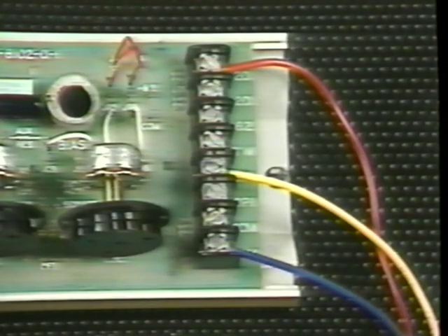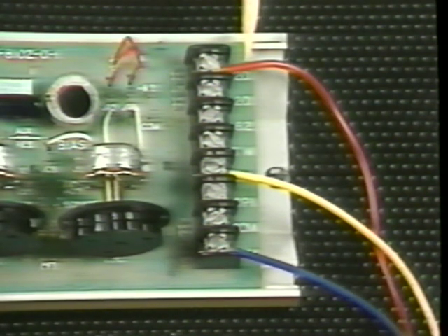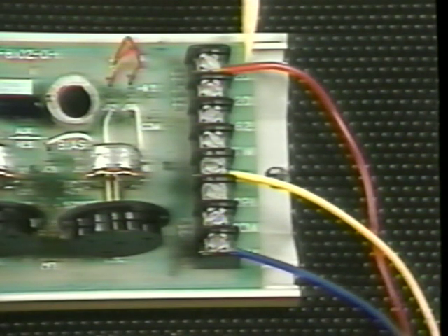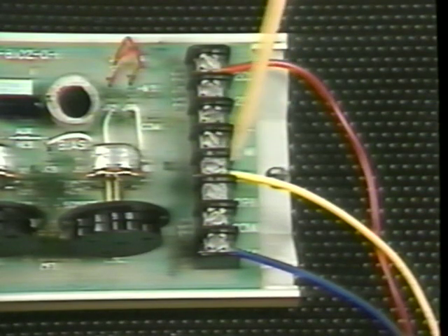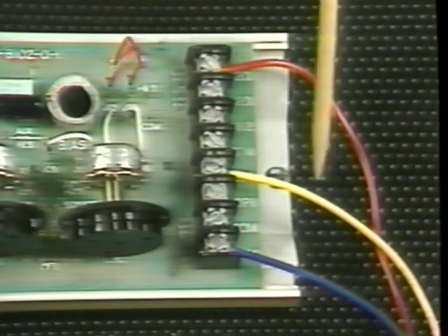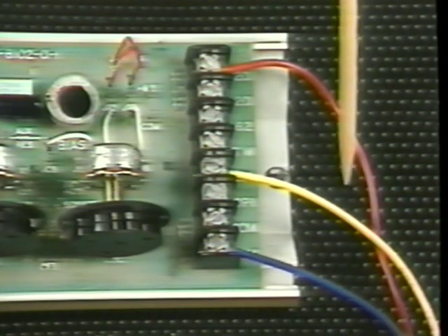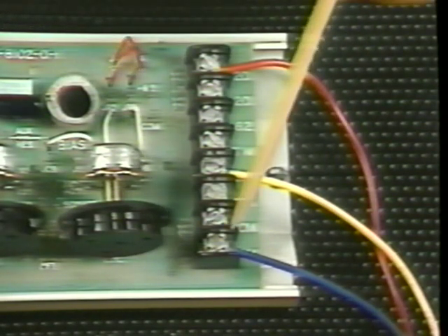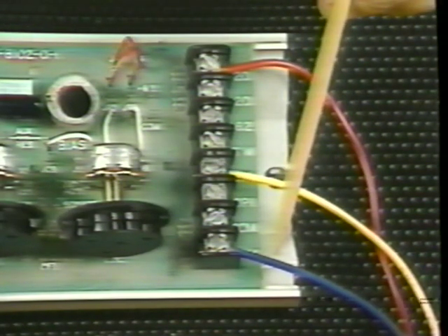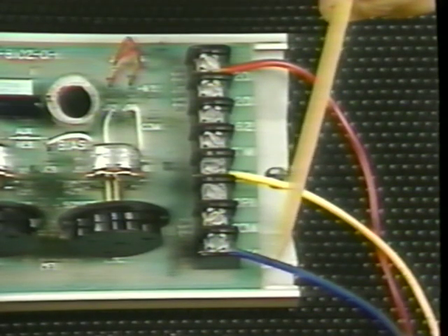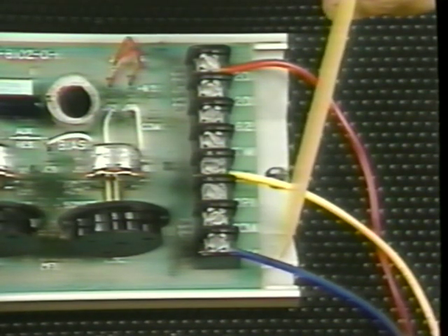The wiring between the controller and control devices is as follows. At plus 20, a red lead indicating incoming 20 volts DC from the one or more controlled devices. At OP1, a yellow lead indicating the 1 to 15 volt DC signal outgoing from the controller to the controlled device. And at the lower common, a blue lead indicating reference for the voltages already mentioned.